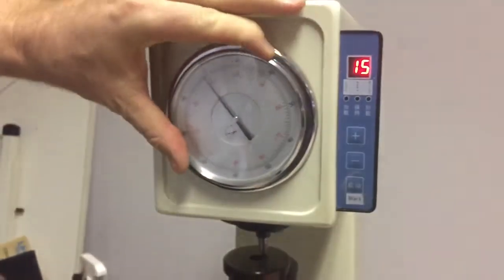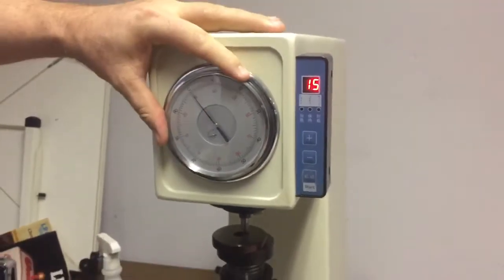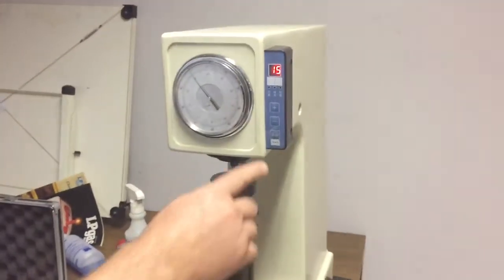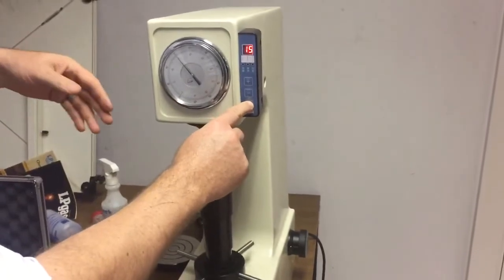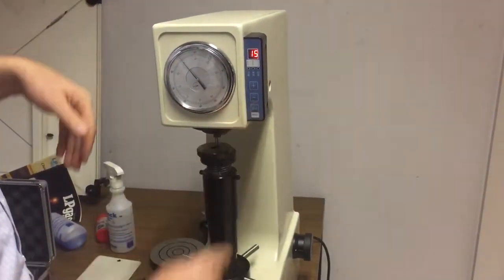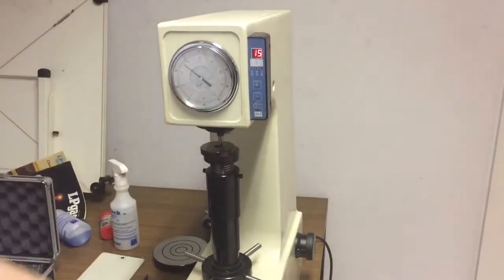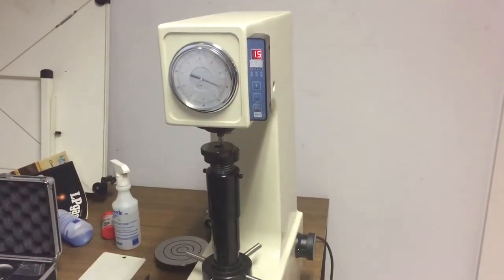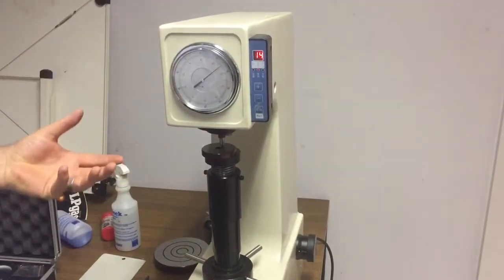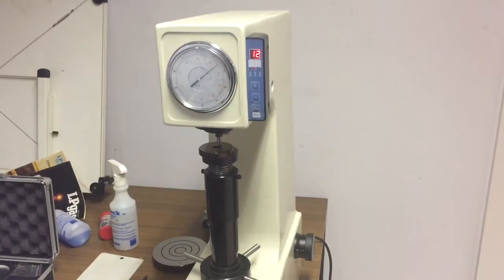You can actually adjust it by playing with the internal settings, but it doesn't really matter anyway. When we press start, what's going to happen is it's going to drive that indenter into the piece using a known weight, and it's going to measure how far the indenter gets driven into the piece.